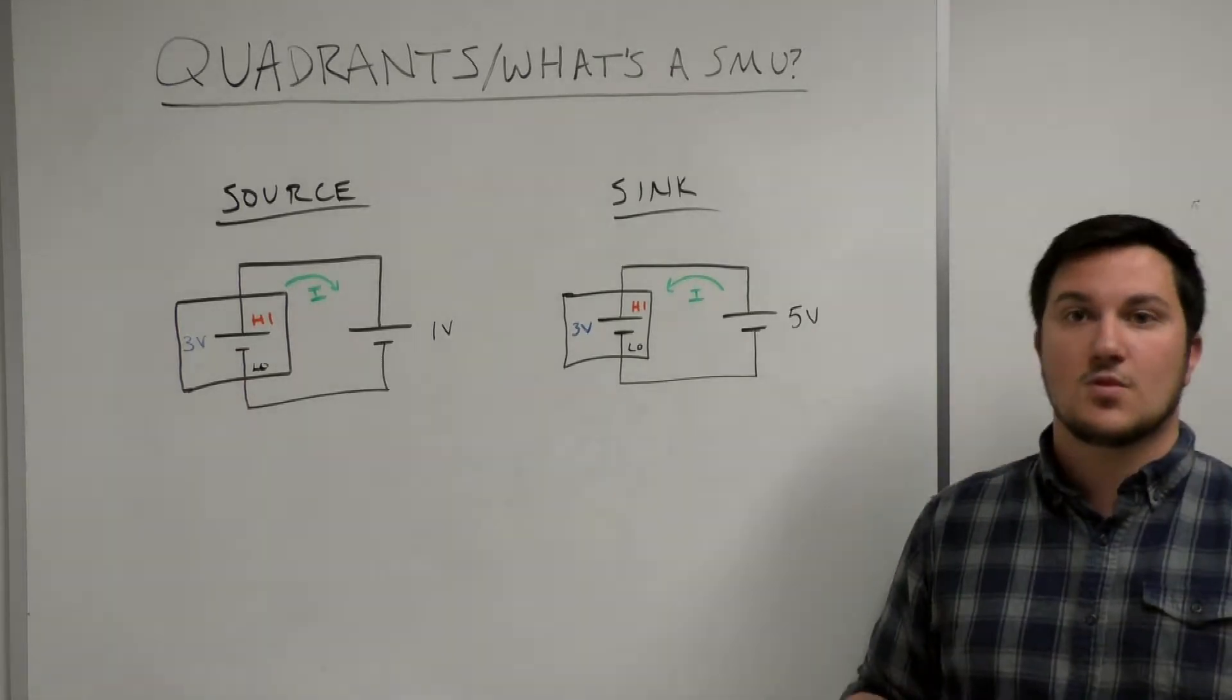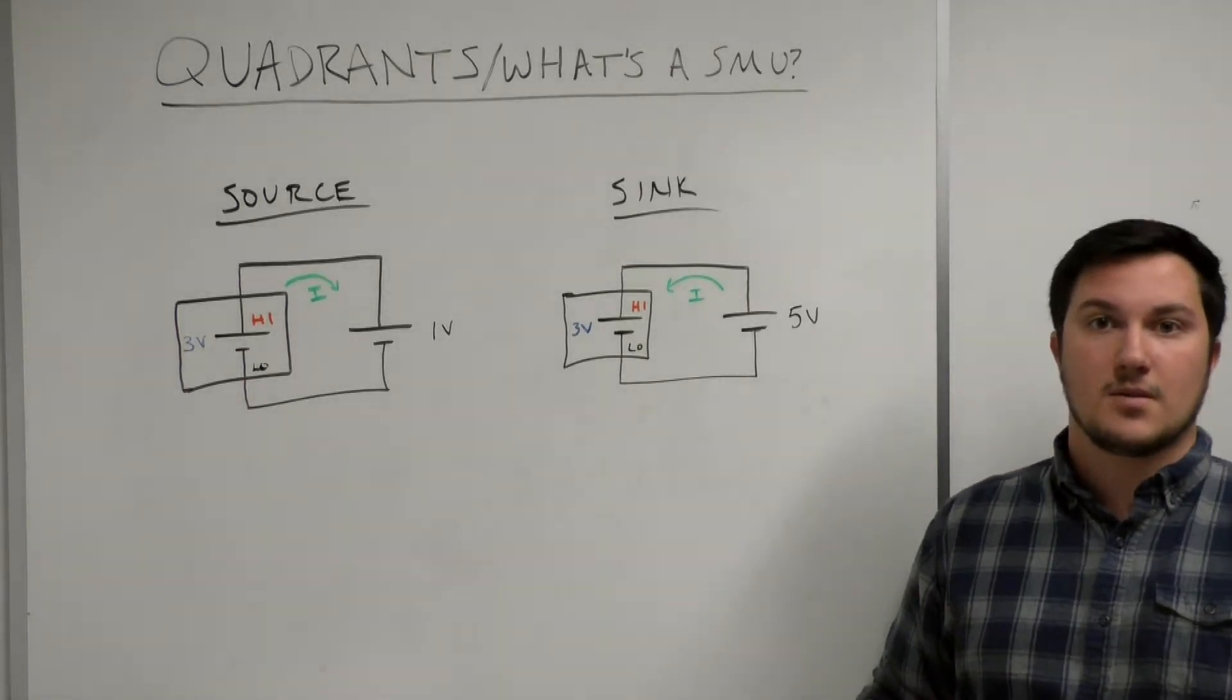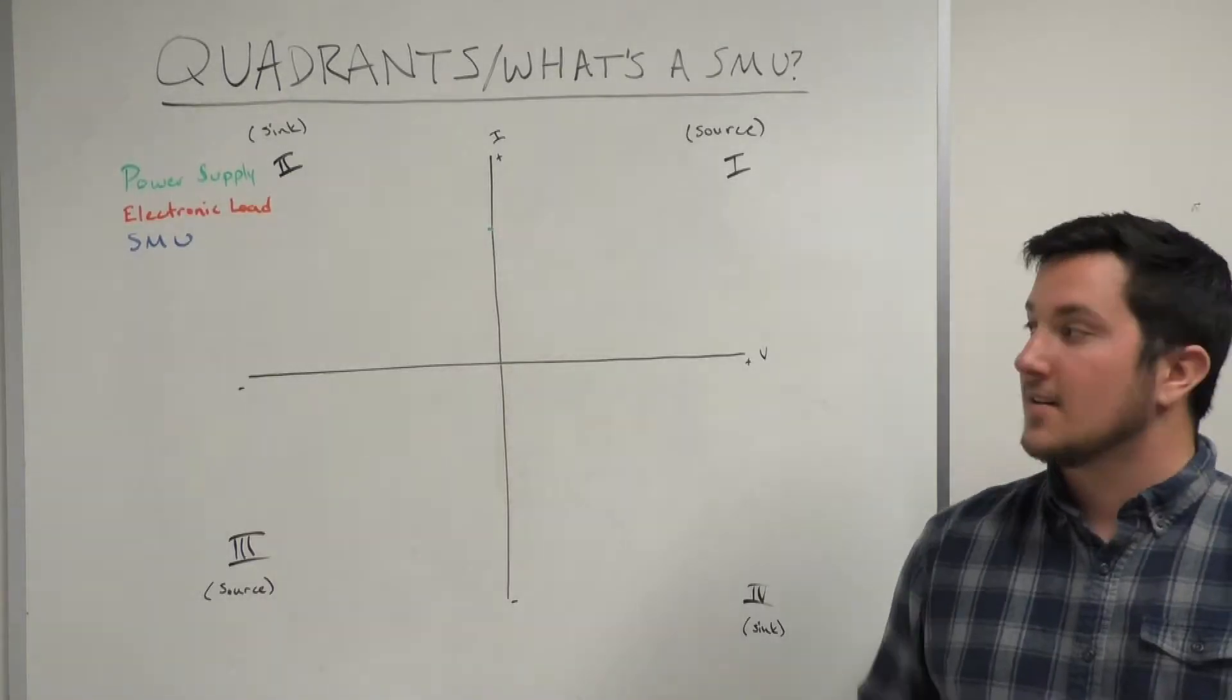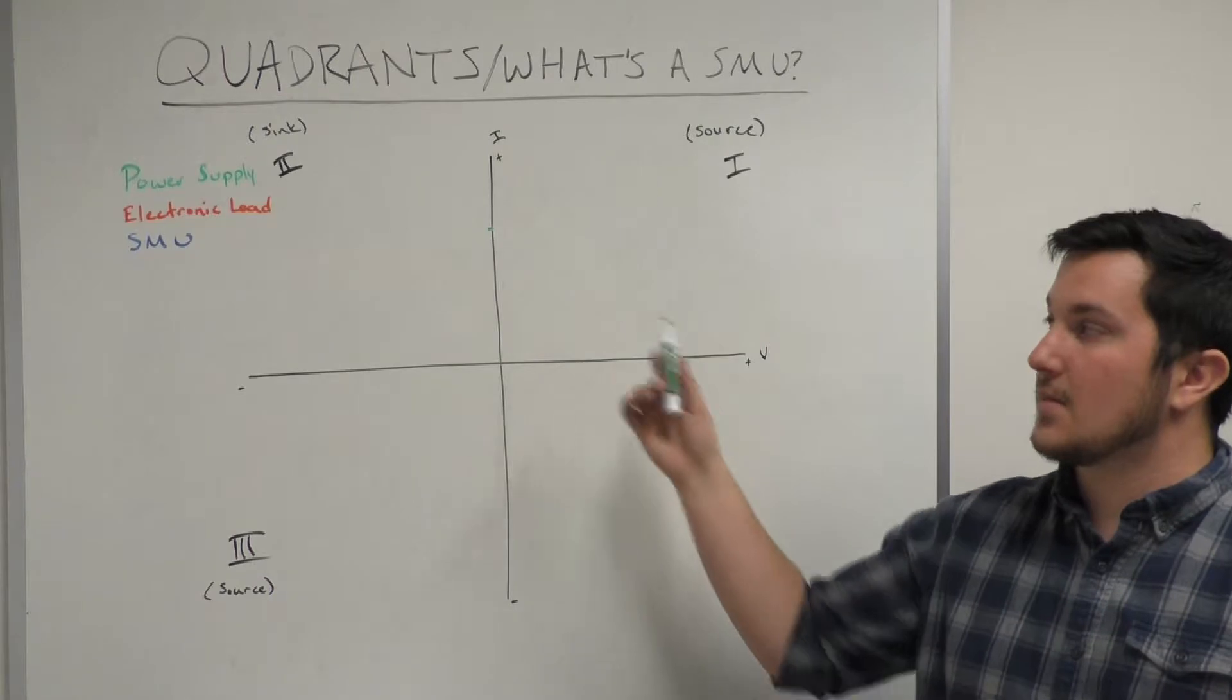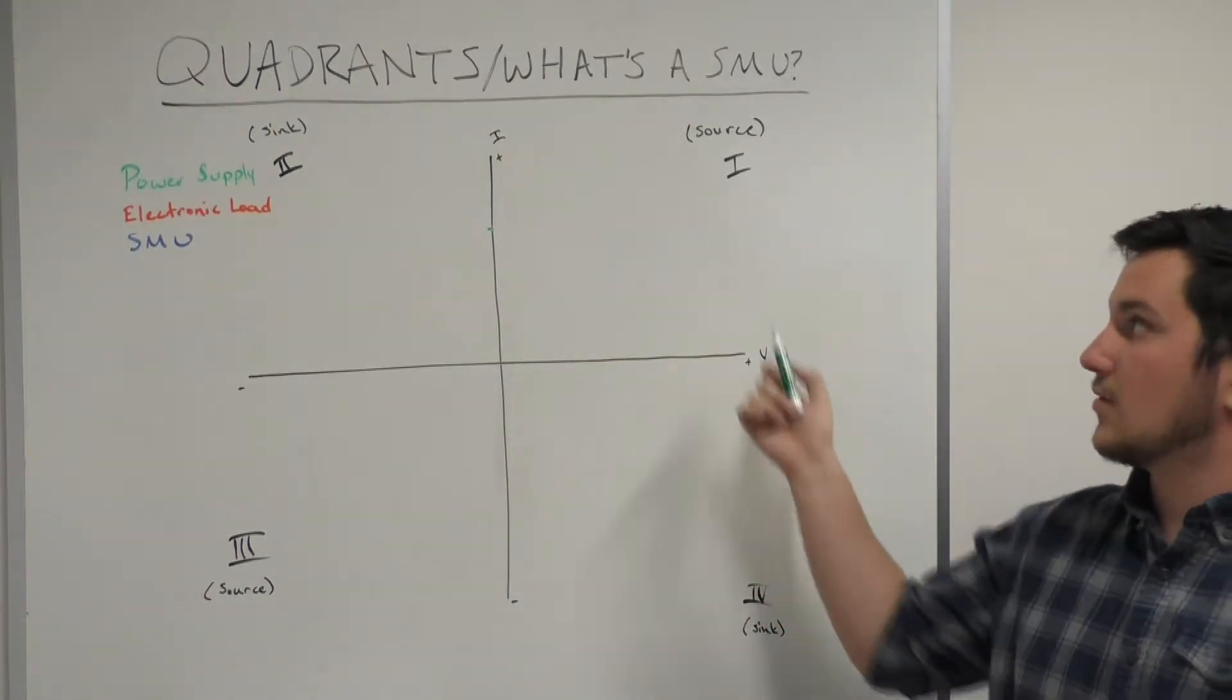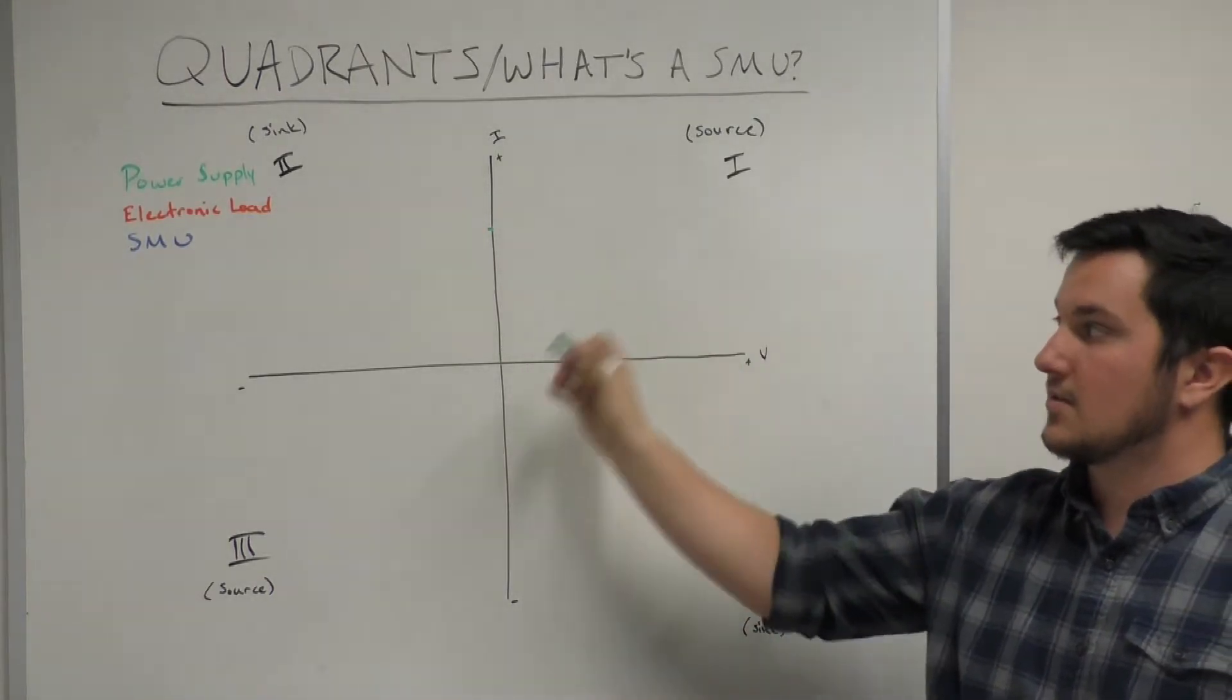Now we're going to take a look at some quadrant diagrams or power envelopes. This is a quadrant diagram or power envelope. It describes the capabilities of an instrument when supplying voltage or current. It's comprised of four quadrants.